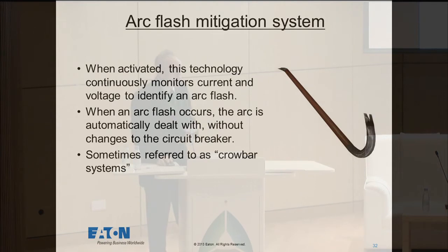Similarly, some manufacturers offer what they call an arc flash mitigation system. And this is a continuous monitoring of the equipment. Some of them are done with light sensors. Some of them use sound sensors to say, when an arc occurs, I want to hurry up and activate something to operate very quickly. And in many cases, they have a high-speed switch that automatically shunts all of the power to the earth, to the ground. So it takes the energy away from the dangerous arc, which is happening downstream, shunts all that energy very quickly to ground, and it prevents the arc from continuing. Sometimes these are referred to as crowbar devices because they crowbar all the current to ground. So another technology that's been developed to address arc flash hazards.